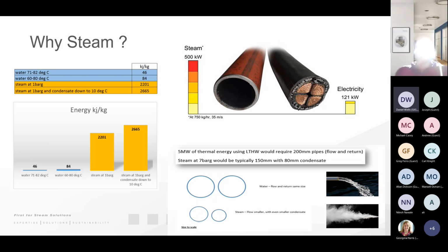Furthermore, we're going to have to circulate a significantly greater mass of water away from the heat pump, meaning that the infrastructure downstream of the heat pump is going to be far, far larger. If we're looking to replace steam with hot water that's generated from a heat pump, we've got to rip out the infrastructure and replace it with a much larger infrastructure. And then we've got a much greater draw of electrical energy from the grid in order to generate that high temperature and then distribute it to the point of use. So if we can find some alternative way to generate steam without a reliance on fossil fuels, then we will have addressed a significant number of challenges that our clients have and help them to retain their existing infrastructure.